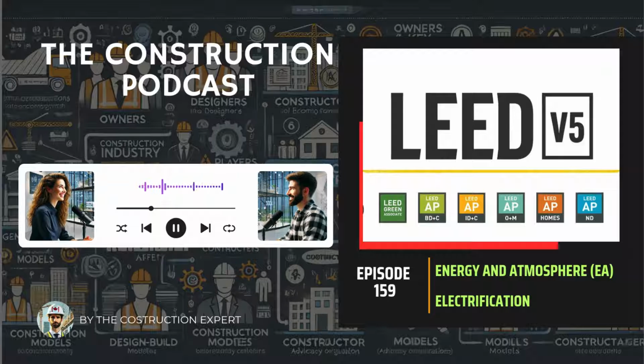Wow, detailed. And the software simulates how the building and its systems perform over an entire year, hour by hour, or even faster. From this simulation, you can calculate the annual average COP for your heating and water heating systems. So instead of one rating at one specific temperature, you get an average across all operating conditions throughout the year. Exactly. It gives us a more holistic, real-world picture of performance, considering part load efficiencies, how systems interact, everything.